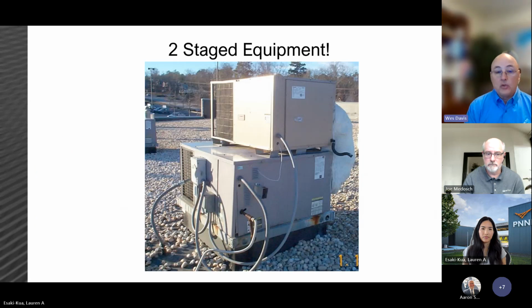Next is equipment. Getting the correct size equipment is very important. You want to make sure you have enough capacity. But in humid climates, if you've got excess cooling capacity, that can create real problems as well. Comfort complaints from cool but damp spaces are clammy, it doesn't feel comfortable. Oversized equipment in humid climates can often lead to fuzzy biological growths that nobody wants or needs. In all climates, oversized equipment leads to excessive starts and stops. This extra wear on the equipment is bad and inhibits its lifespan. HVAC equipment is made to run, and like highway miles for your car, it's meant to have a nice long run cycle, especially during the summer months, or for furnaces in the winter months.